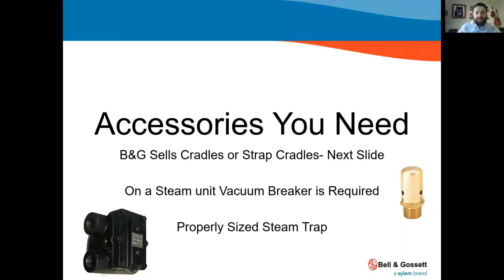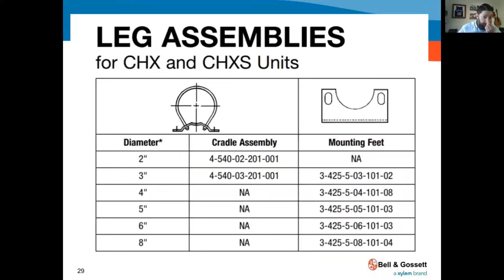And you need a properly sized steam trap, which makes sure no steam leaves the unit and gets into the water where it can flash and create damage. It has a float, so only the condensate water is leaving. So this is what the assemblies look like for the legs and the cradle. Basically, you're just going by the diameter of the unit. So you can either do that cradle and strap it up high, or you can get the mounting feet. You need to purchase 2 of these per unit. They don't sell them in pairs.